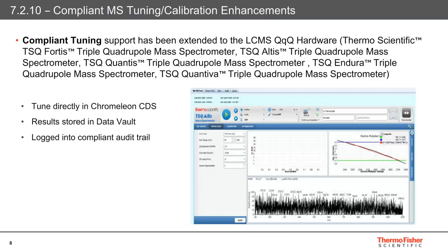Another feature that ties not only to bioanalysis but adds further security to Chromeleon CDS is compliant tuning. This feature now covers the following Thermo Scientific triple quadrupole mass spectrometers: the TSQ Fortis, TSQ Altis, TSQ Quantis, TSQ Endura, and the TSQ Quantiva. It allows the function of tuning or calibration to be accessed directly from a Chromeleon ePanel, with the results being stored securely in a Chromeleon Data Vault. The actions are also logged into a compliant audit trail, and when this feature is activated, it is not possible to access a tune application outside of the Chromeleon software.